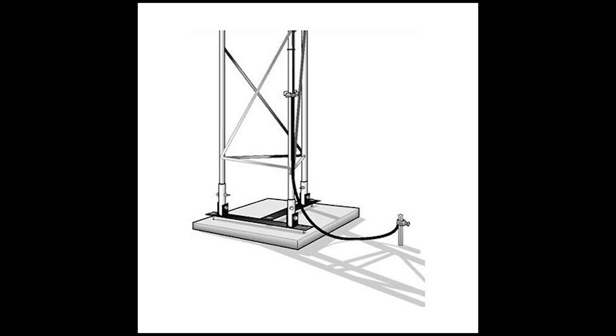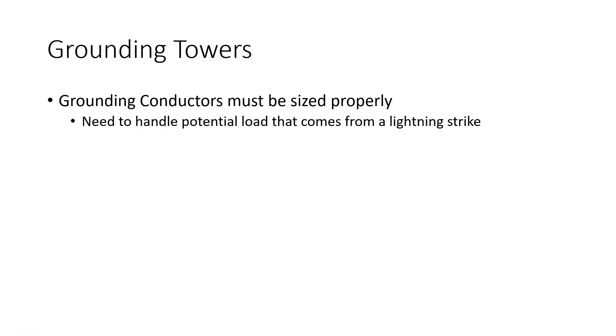Extra care should be taken when grounding any type of tower, mast, or monopole because of the danger that they can present, especially in regards to lightning strikes. It is important to ensure that when grounding any type of tower structure, the grounding electrode conductors be sized properly so that they can handle any potential load that the tower may encounter.